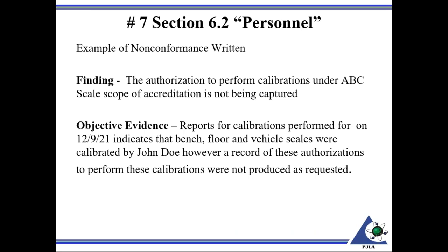An example of a non-conformance written here would be, like I stated, once someone is trained and an organization determined that they can perform the test or calibration independently, that individual would have to have a record that they are authorized to do so. I changed the names on these examples and companies' names, as you could probably tell, for confidentiality.